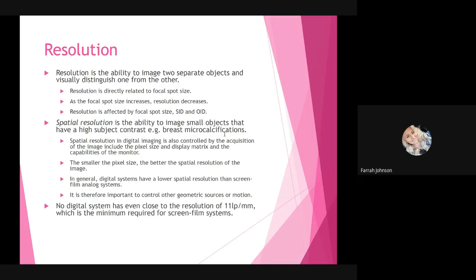In general, digital systems have a lower spatial resolution than screen film analog systems, and it is therefore important to control either other geometric sources or motion. No digital system has even close to the resolution of 11 line pairs per millimeter, which is the minimum required for screen film systems.